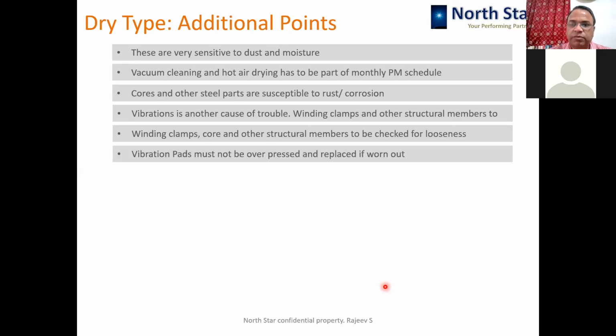Vibration pads normally are provided at different locations in the dry type transformers. So those vibration pads are to be checked visually for deterioration or over compression, because after some time the pads become rigid and they won't absorb the vibrations.